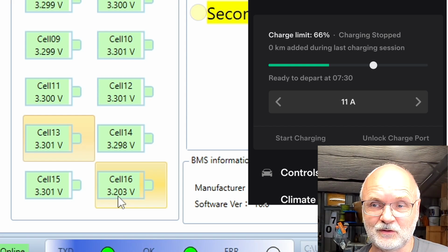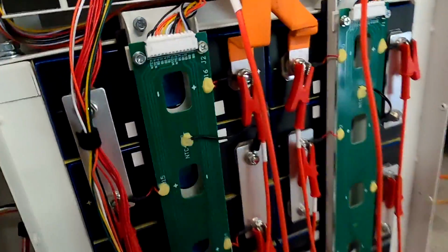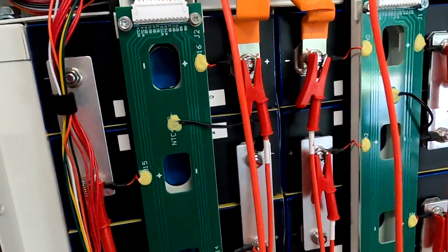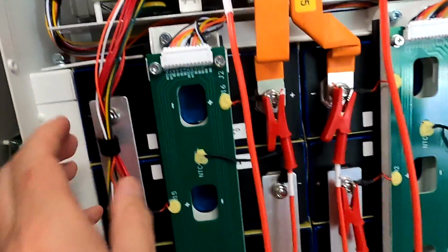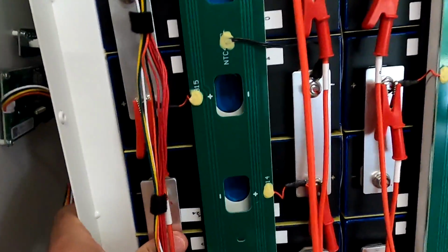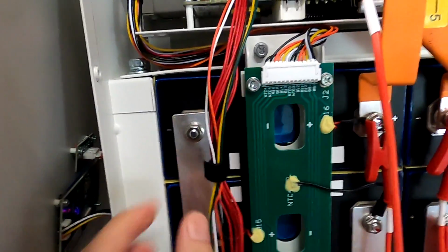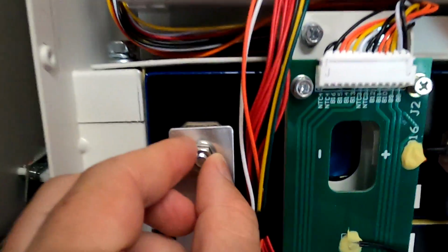We check the connections on cell number 16 again. Cell number 1, cell number 16, there's this one up here. Oh yeah, this bus bar, this bus bar is hot. Oh, look at this, loose connection and not marked.